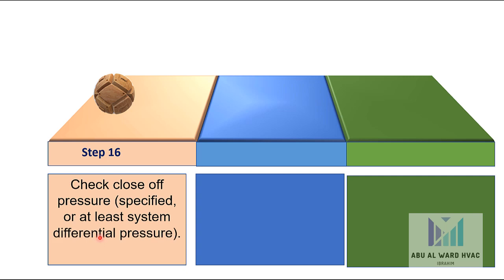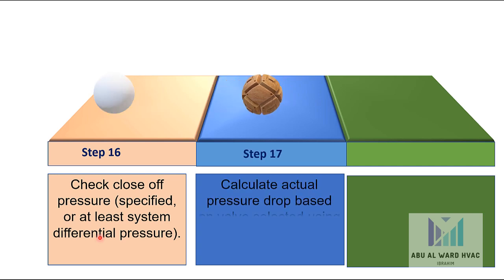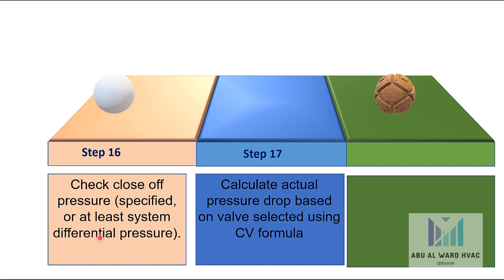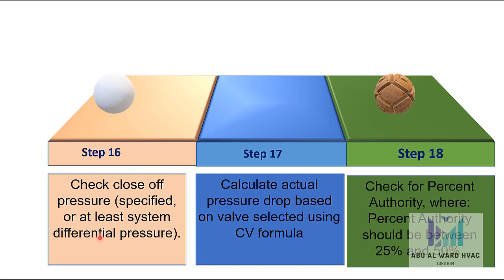Step 14: Determine if manual override is required. Step 15: Based on all of these inputs, select an orderable valve assembly. Step 16: Check close-off pressure — specified or at least system differential pressure. Step 17: Calculate actual pressure drop based on the valve selected using the Cv formula. Step 18: Check percent authority — it should be between 25% and 50%.